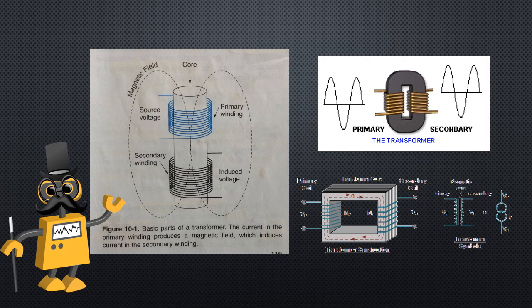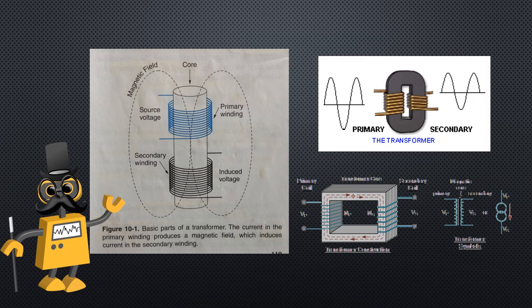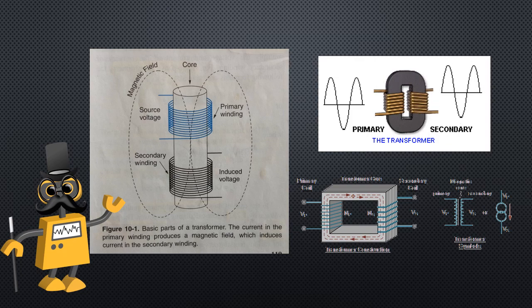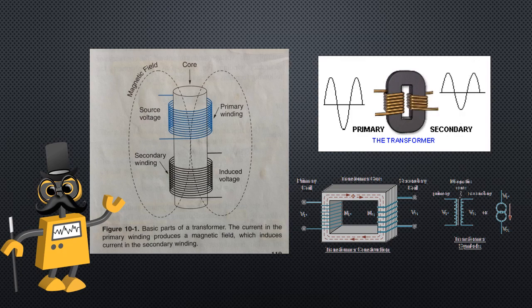There is a direct relationship—the voltage ratio between the primary winding and the secondary winding. The number of turns of wire in each coil determines the ratio. For example, if a transformer has a 10 to 1 voltage ratio, one coil has 10 times as many turns and will produce 10 times the voltage. The voltage ratio is also called the turns ratio. If the primary has more turns than the secondary, it is a step-down transformer. A step-up transformer has more turns in the secondary and produces a higher voltage than the input.